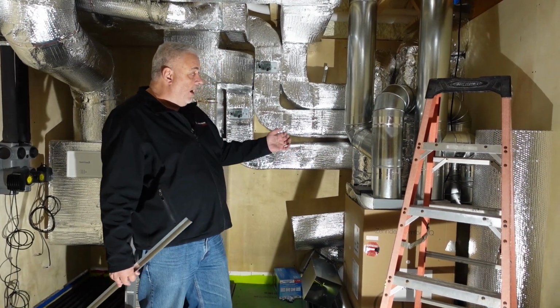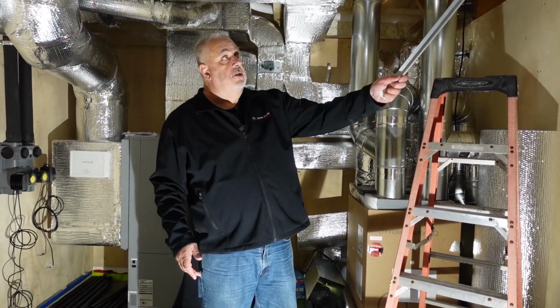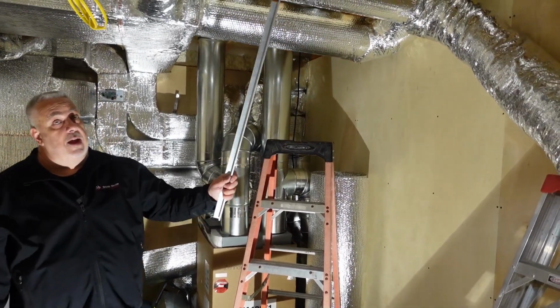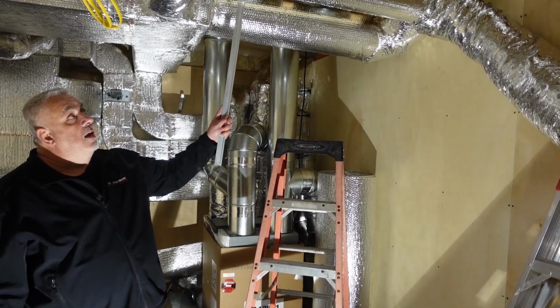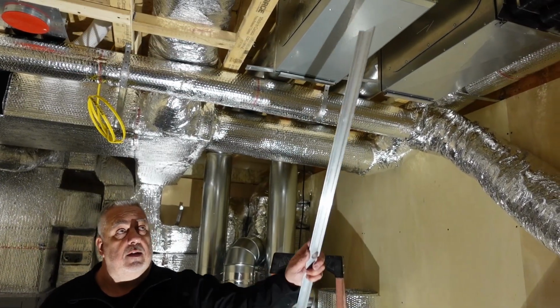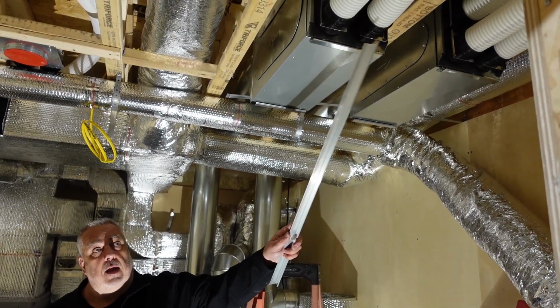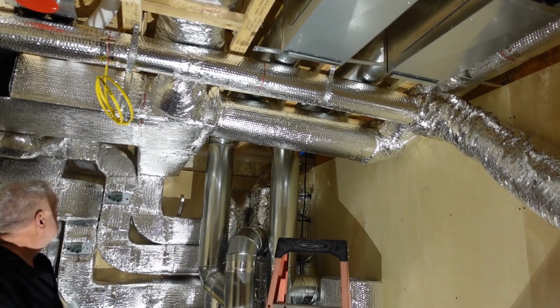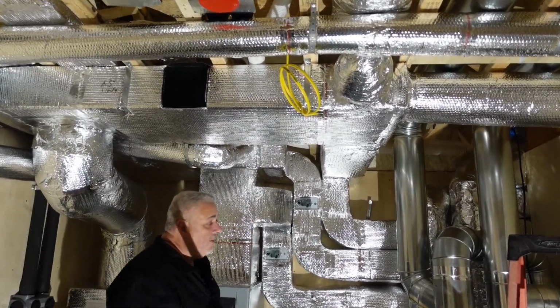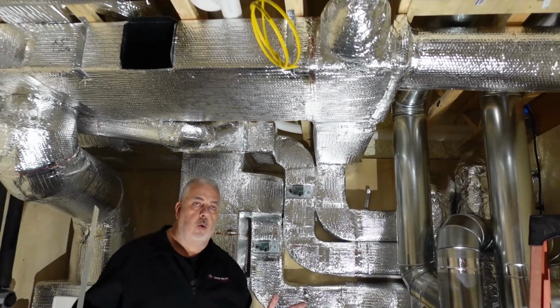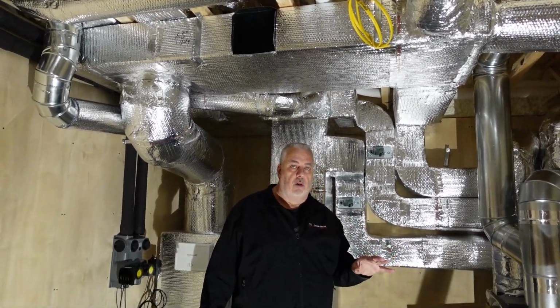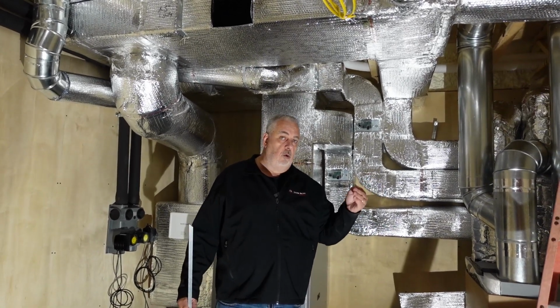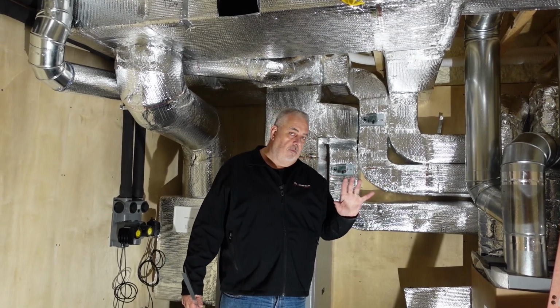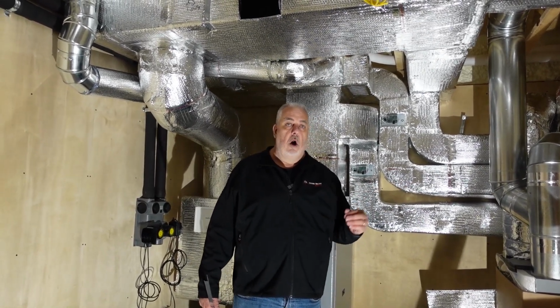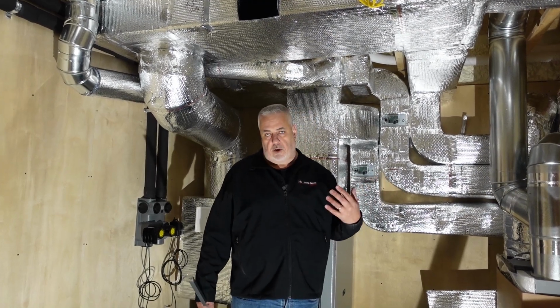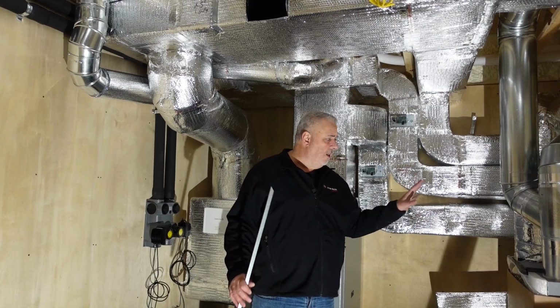Now, that air, once it gets extracted and placed on that incoming air, it goes up to a series of manifolds. You can see the manifolds here. What the manifold does is take the large supply of air and break it down into this series of comfo tubes, which snake around the house delivering probably on the order of 20 CFM plus or minus per outlet. So in some rooms you'll see there might be 2 or 3 outlets, so we're getting 40 or 60 CFM supply to that room, or if there's 2 pipes extracting, we're extracting 40 CFM. But it's a fully balanced system.